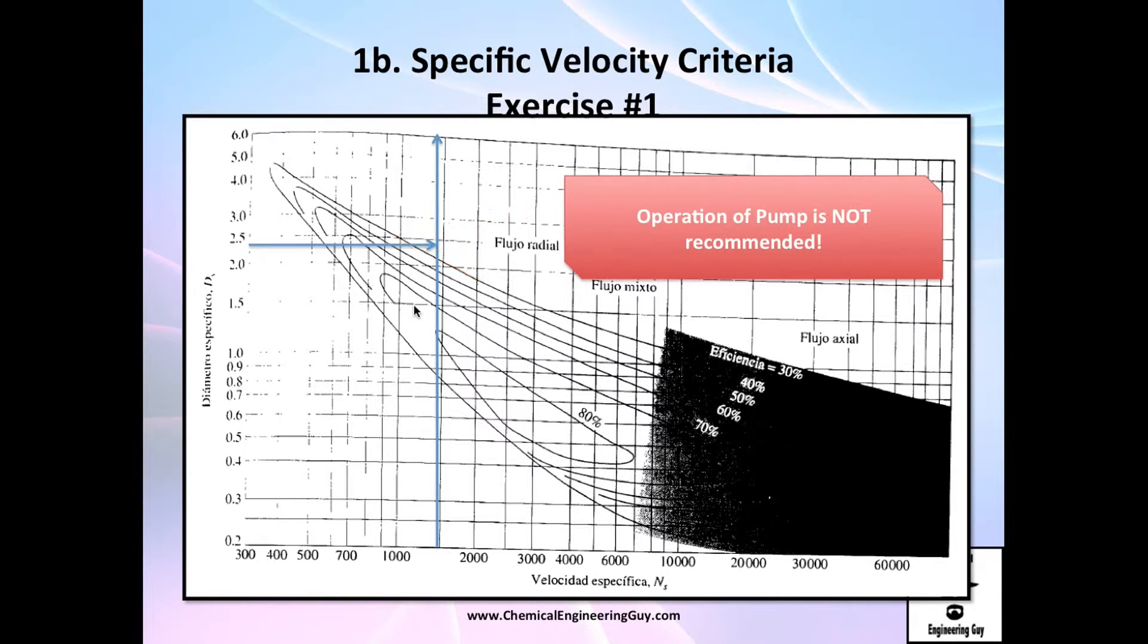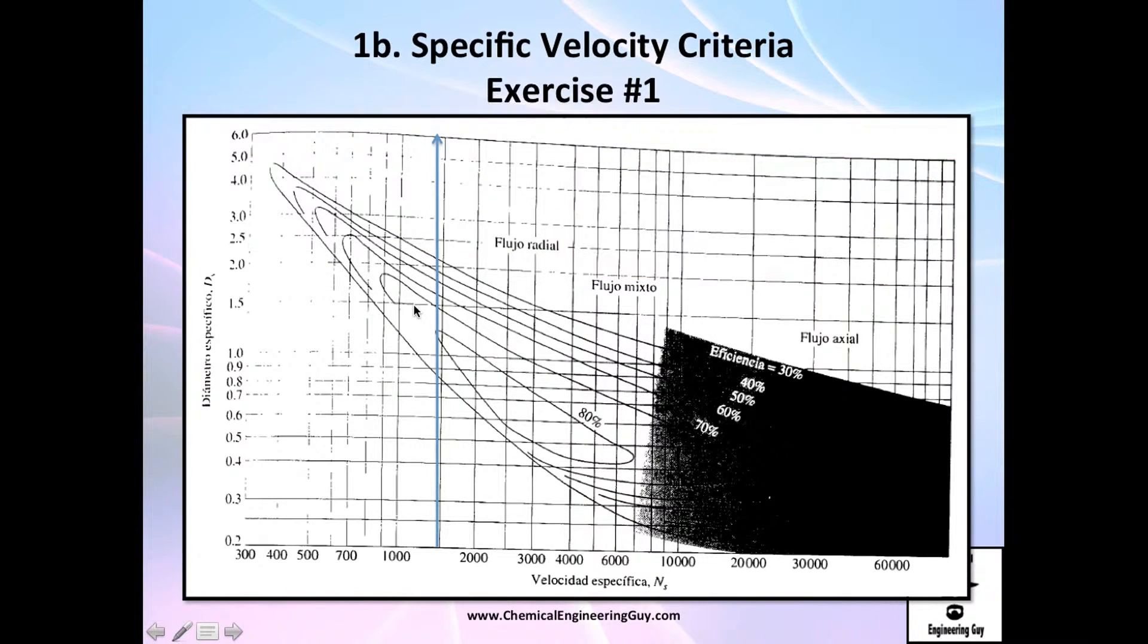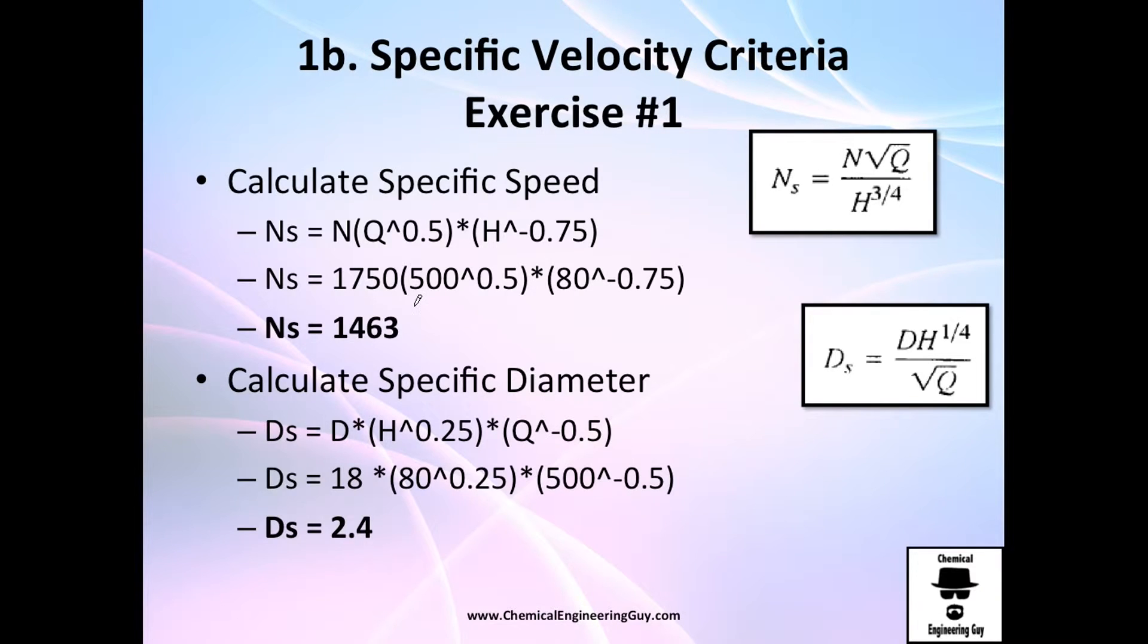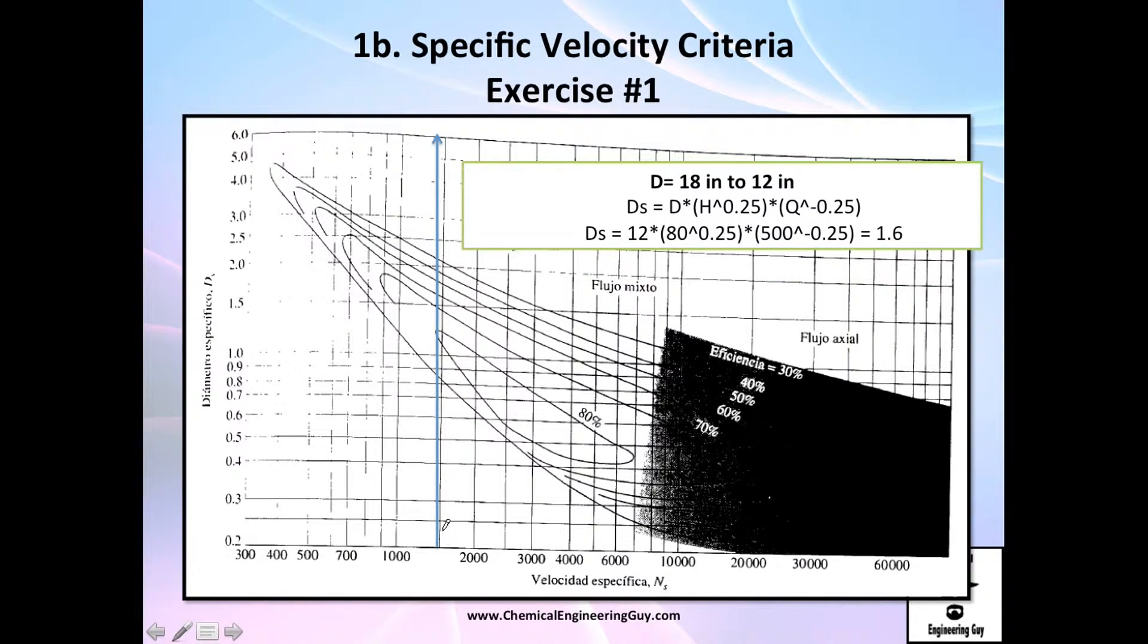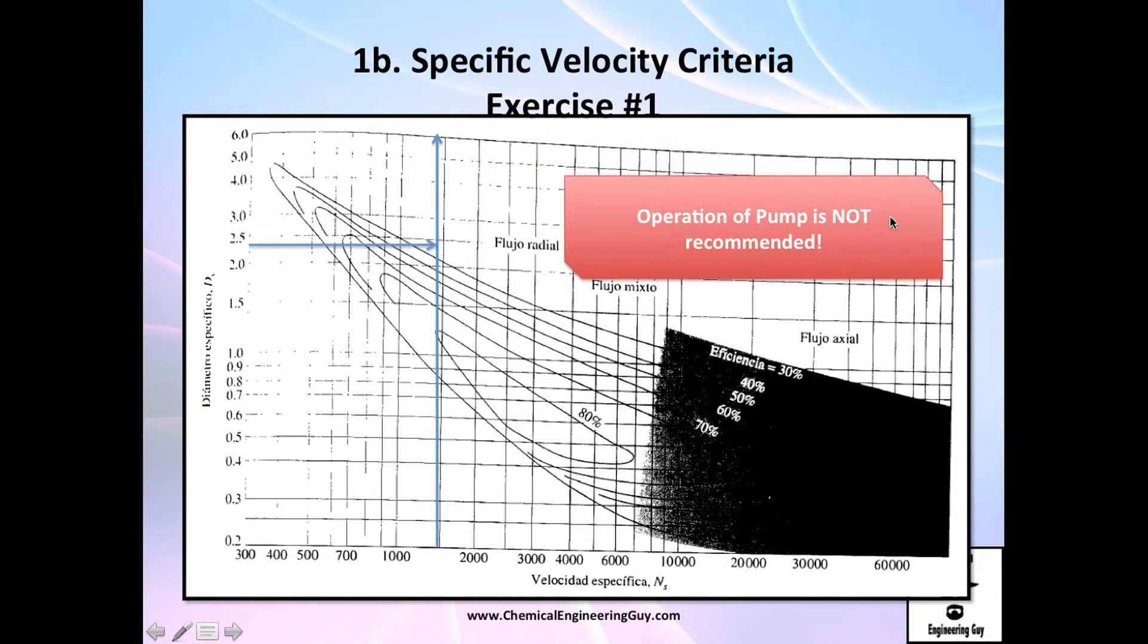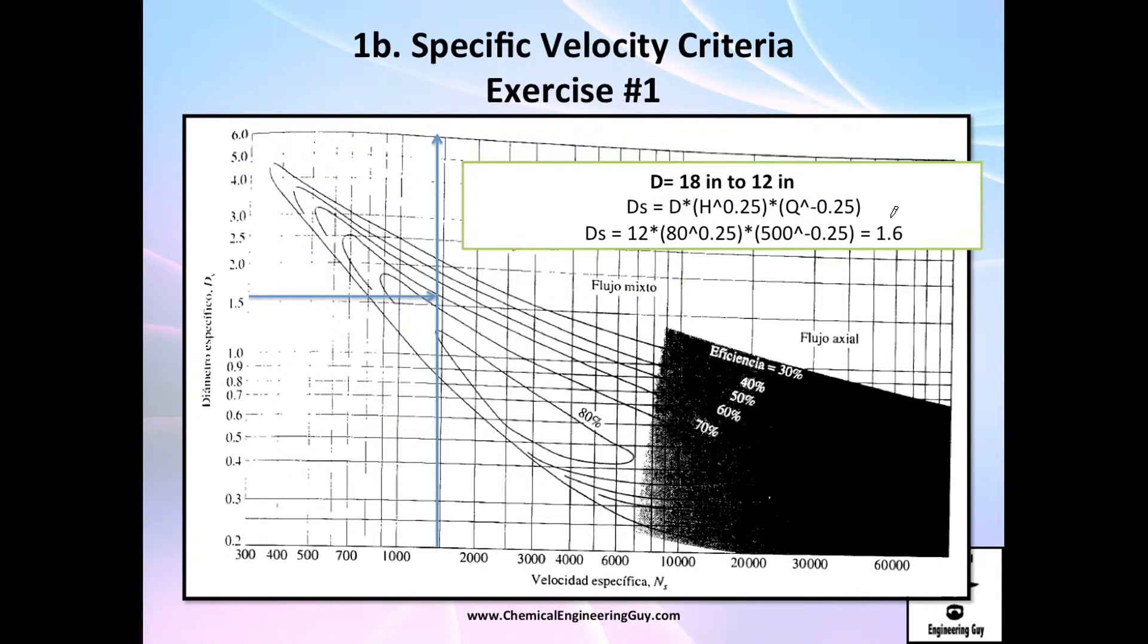So one thing that we can do is to reduce the size of the diameter. Recall that we got 18 inches. So what would happen if we use 12 inches. Let's do that. 12 inches instead goes here. And I found out that my new specific diameter is 1.6. So from this point, now I got it inside.